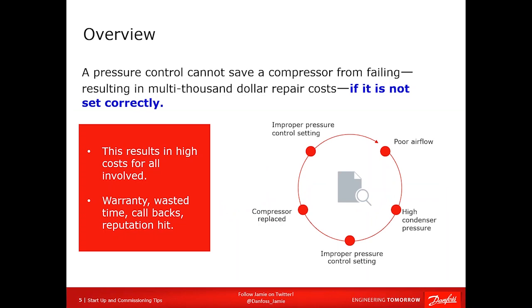So if you do not catch these underlying issues, if you miss, in this case, the pressure control that is not set properly, or expect that pressure control to save the system when there's a charge loss, it's not going to happen. What will happen is you will have failure, you will have callbacks, or you will have poor performance. This happens all the time in the statistics.